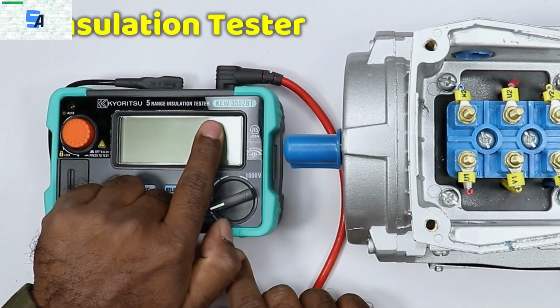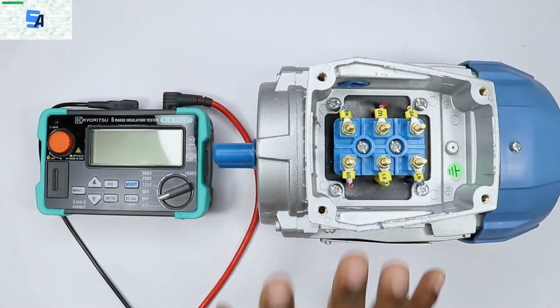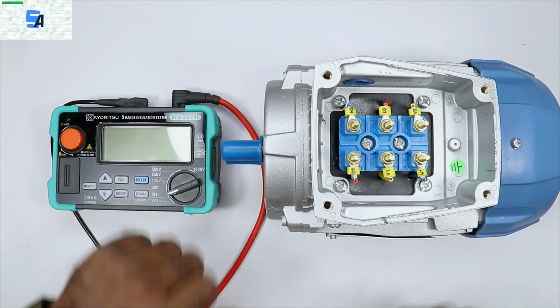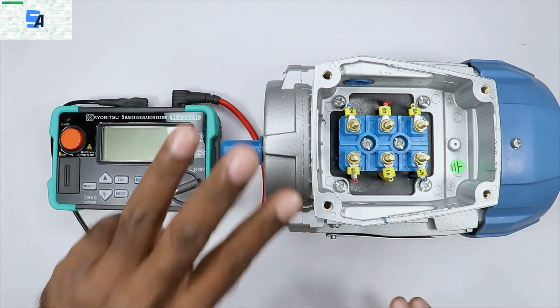Friends, as you know, for the motor we use, if any problem occurs in the winding of the motor, then first of all this type of insulation tester is used to check the motor. So how to check this motor? Let us learn this. To check any motor, there are a total of 3 ways.